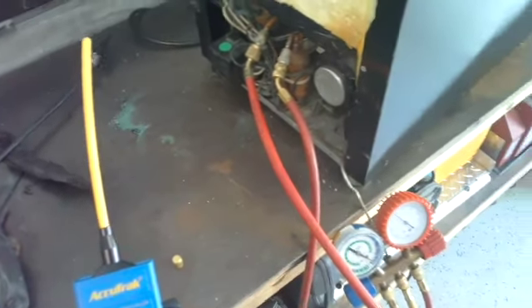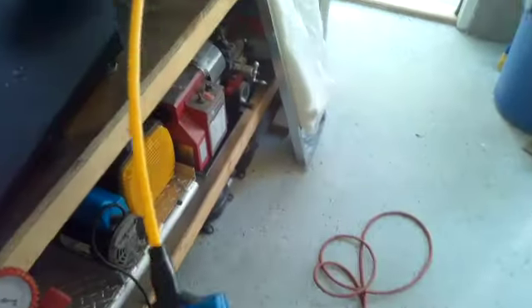I've checked the evaporator coil or the plate. Could not pick up anything in here anywhere. Normally when you have a leak you'll probably see oil, but not necessarily so. Or maybe a chip on the evaporator plate. I'm not finding that. And I'm checking everything.